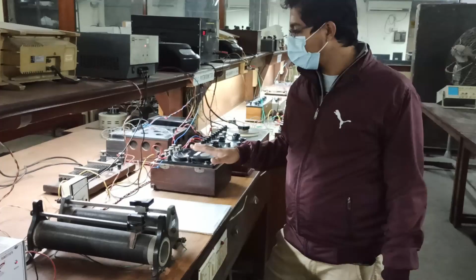So by varying this RH1 further, we can change the wattmeter reading. We can change the watt to 40 watt, 60 watt, 80 watt and 100 watt and do the same process for all those watts to calibrate this wattmeter. And thereafter we will calculate the true wattage and get the error of the wattmeter. In this way we can calibrate this dynamometer type wattmeter using this DC potentiometer.